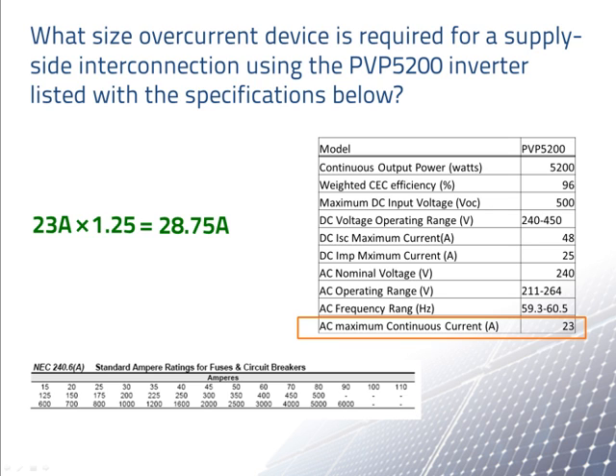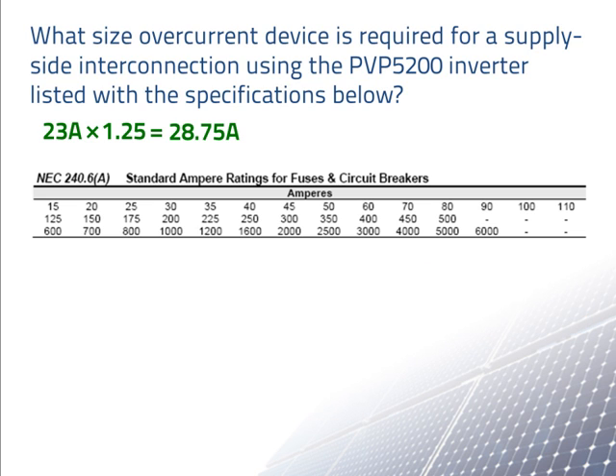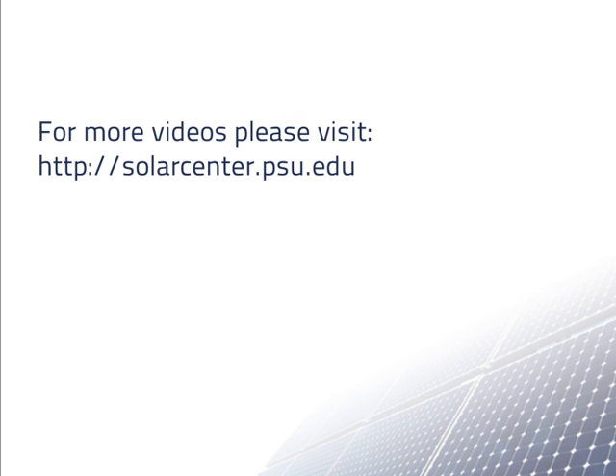NEC standard 240.6 lists standard ampere ratings for fuses and circuit breakers. NEC 240.4 permits the next largest standard size overcurrent protection device to be used. The next highest size above 28.75 amps is 30 amps.